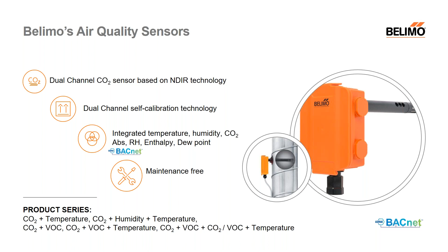All of our CO2 sensors also have a NEMA 4X IP65 rated housing as standard, which helps protect the sensor from these harsh grow environments. Our sensors also are all maintenance free, and depending on exactly what you need, we also offer combination sensors that also include CO2, humidity, temperature, and VOC, otherwise known as volatile organic compound measurements, all within the same unit. Towards the end of this presentation, I'll also go over in detail what these combination sensors can include. So again, as stated before, we do also have a grow farm specific measurement range that can measure CO2 values up to 5,000 parts per million.